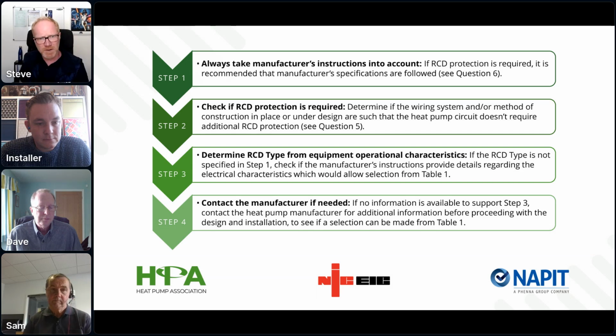So by following part 5 of those certain things, like I said, with the weight, the cable that's wiring it, that will be specific to the actual supply to the heat pump. No, it's interesting. So step 2 is to check if an RCD is required. So does that suggest that it's possible that an RCD might not be required in some circumstances?